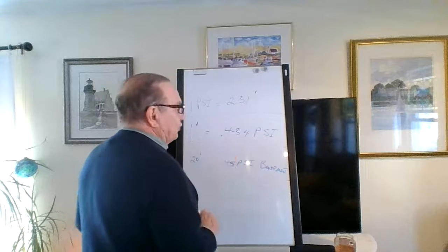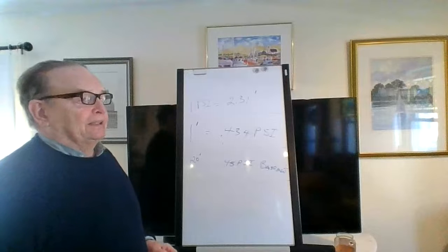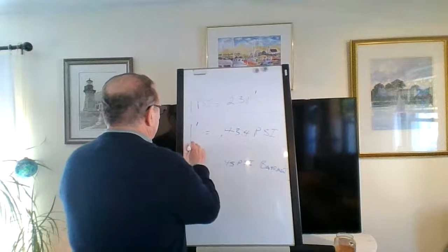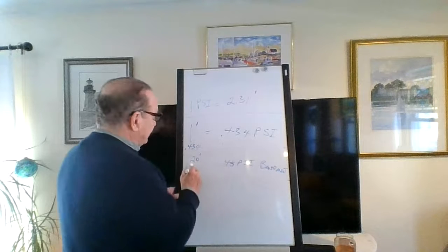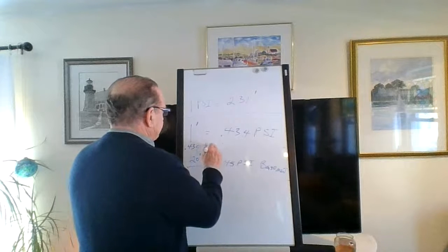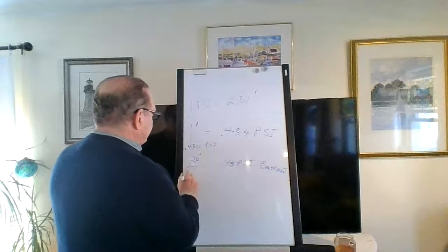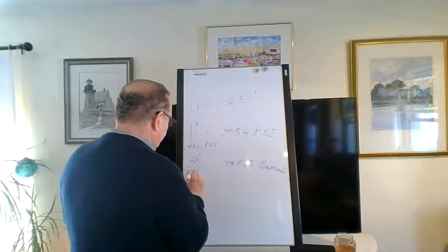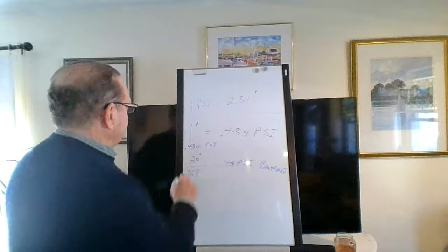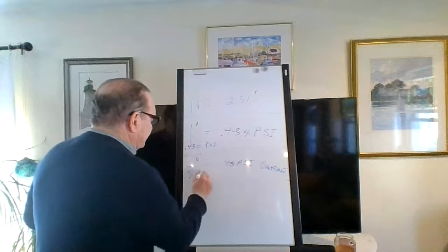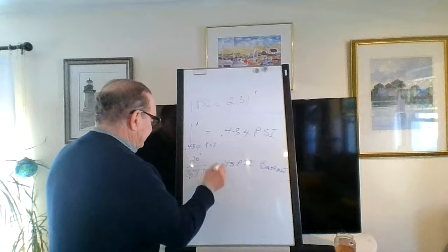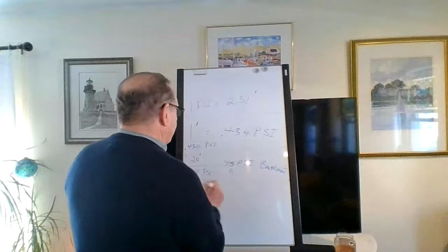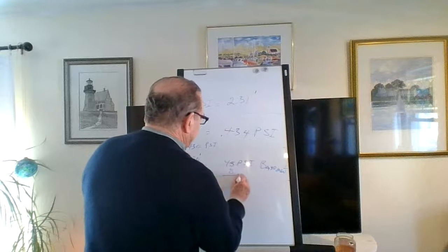All right, 20 feet. And each foot is 0.434. Remember, PSI. So what is that? It's going to be 868, right? So if I multiply this out, it'd come out to 8.68 PSI. Have to deduct that right here, right? 8.68. All right, I'll just make it 8.